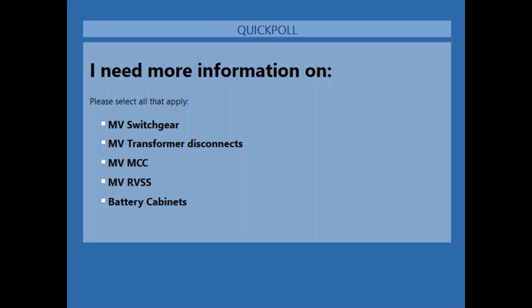Thank you. Well, also, Michael, one thing I'll point out too, if it's just a switch, if we're building it, we can also have side access covers. That can be fleshed out during the design process if you want to have the ability to stand to the side and have an access cover on the side to do your cable terminations. Same thing on the switchgear, or we can make front and rear access panels so you can access the rear. So there's a lot of creative things we can do with switchgear and metal enclosed fused switch construction to give you easy access for connecting the cables and maintainability. Just as long as we know you want that there, we can do it.